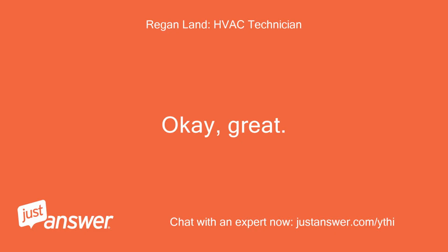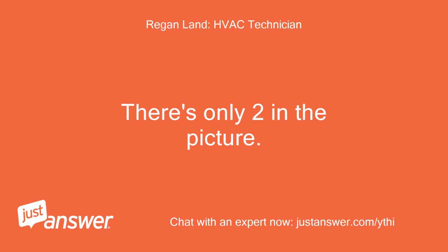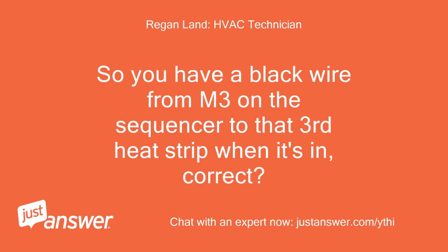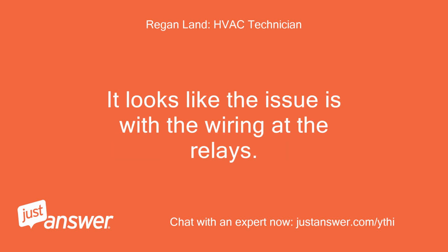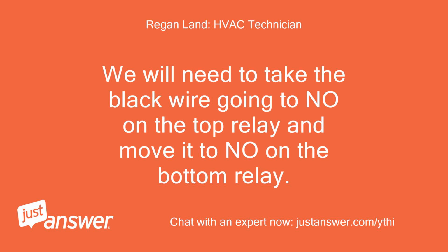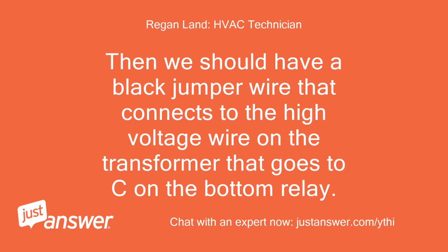Okay, great. There's only 2 in the picture. So you have a black wire from M3 on the sequencer to that third heat strip when it's in, correct? It looks like the issue is with the wiring at the relays. We will need to take the black wire going to NO on the top relay and move it to NO on the bottom relay. Then we should have a black jumper wire that connects to the high voltage wire on the transformer that goes to C on the bottom relay.